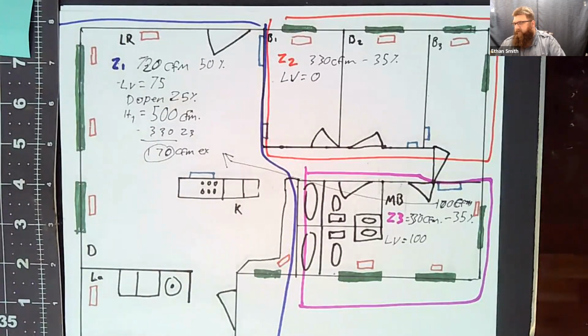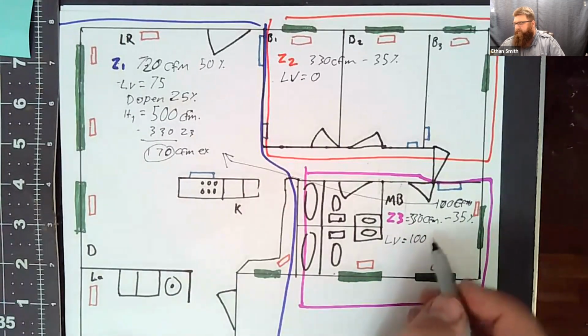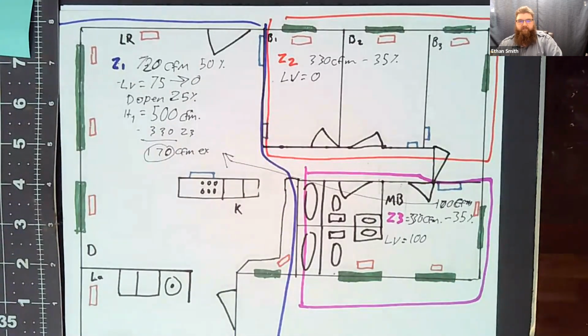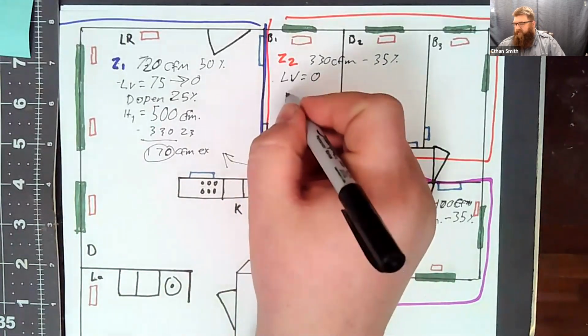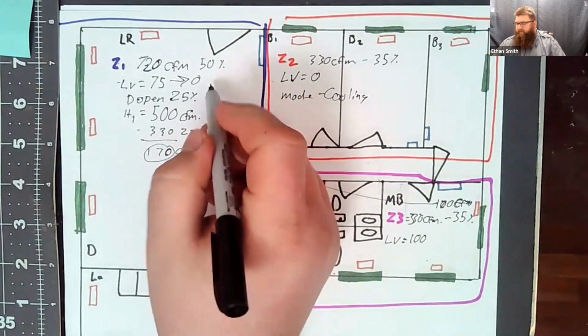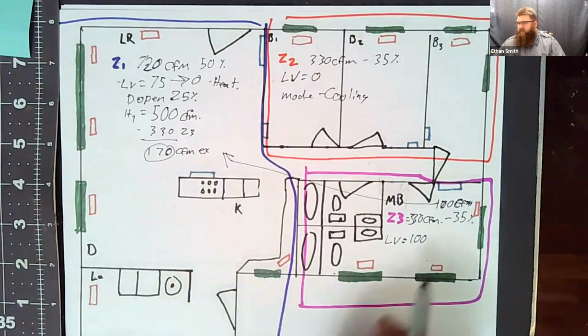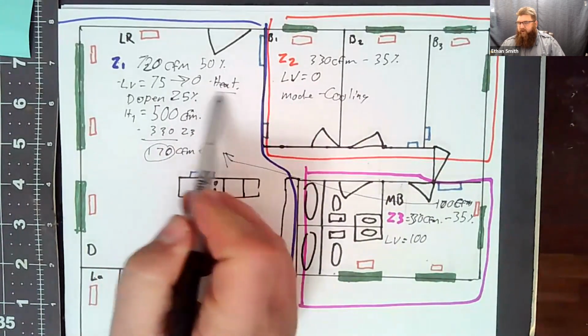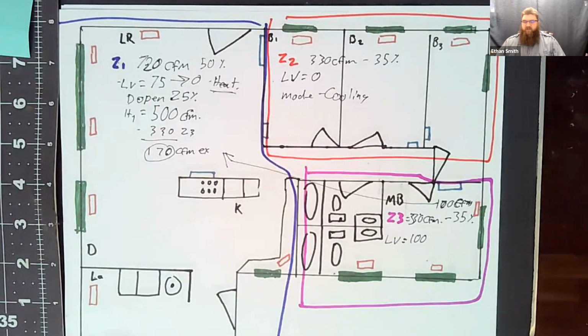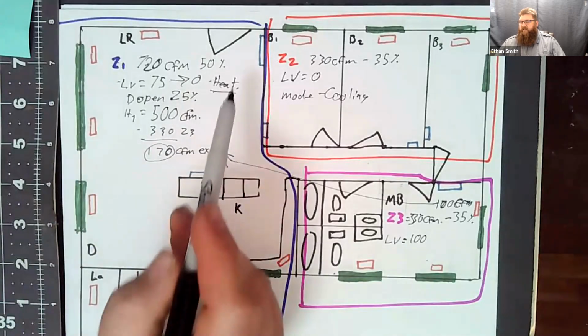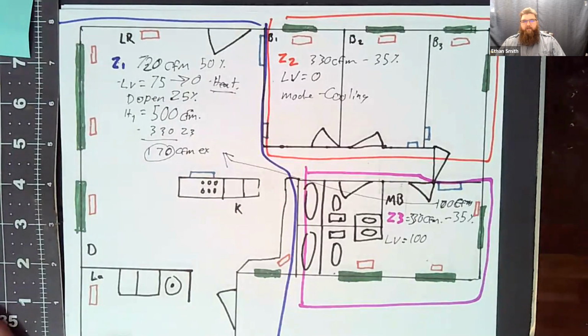Okay. Now, if it comes to the point where zone 3 is still calling and my load value goes to 0 because we've been dumping some heat in there. Okay. Now my intelligent relief strategy is going to look to see which mode the zones are in. So if zone 2 isn't calling because it's in cooling mode, but zone 1, even though it's not calling, it's in heat, it's going to say, okay, now I'm going to take my excess air and put it into any zone that's in the heating mode. Okay. So even though I don't have load value anymore, I've satisfied my load value, it's still the prime candidate for intelligent relief because it's in the heating zone.